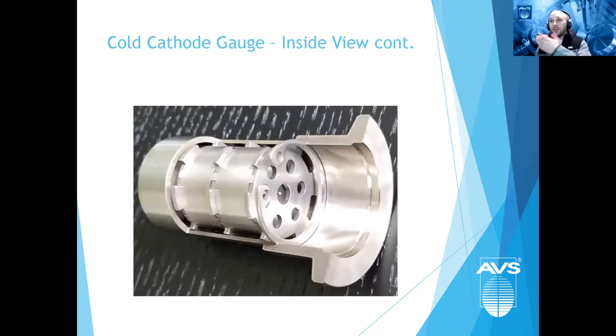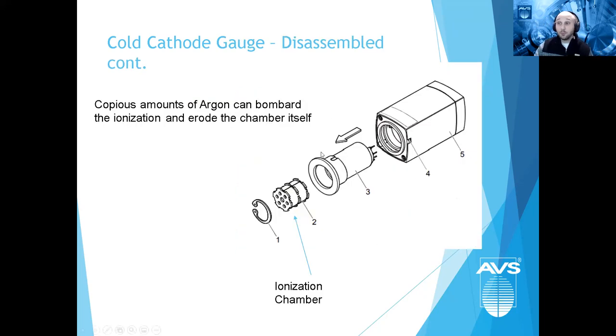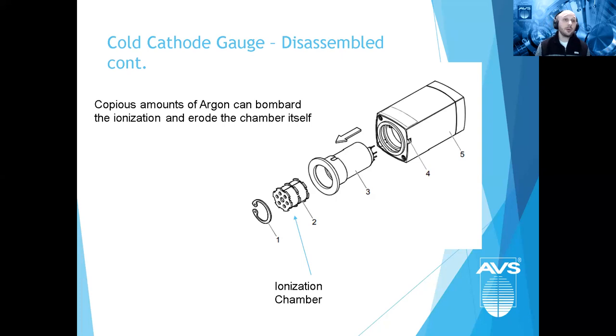A contaminated cold cathode shows a rainbow effect internally. Contaminated cold cathodes typically measure lower pressures than actual. You can remove and physically scrub a cold cathode clean. However, if you have copious amounts of argon with a cold cathode, you can bombard and erode the ionization chamber — so in argon-heavy applications, use a hot filament instead.